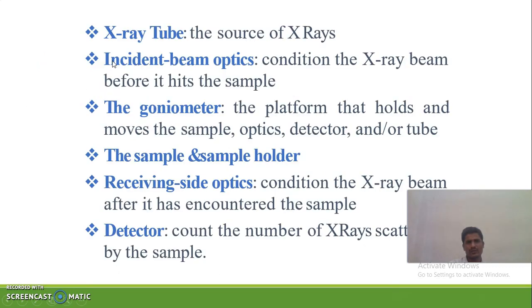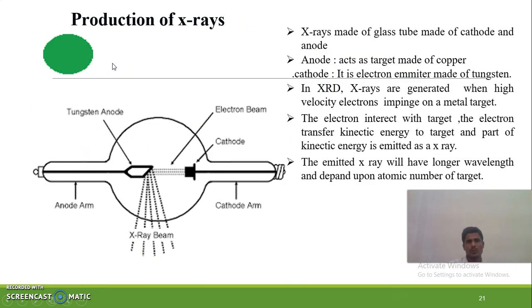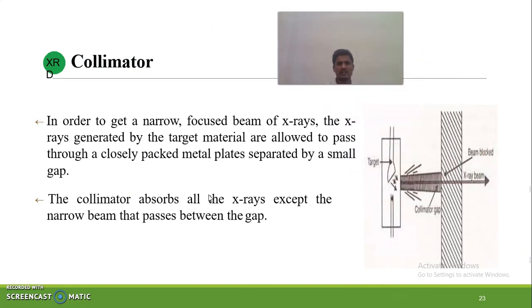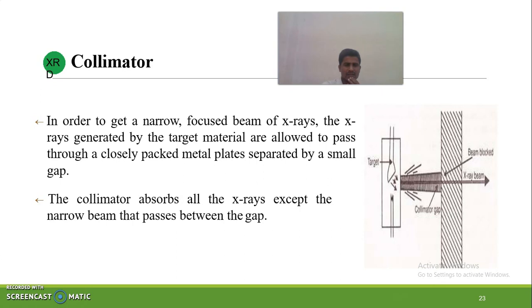The role of the collimator: whatever the X-ray beam produced is not narrow — it is broad. In order to obtain a narrow beam, it must pass through a small collimator. The collimator absorbs all the X-rays except for the narrow beam that passes through the gaps. Broad X-rays are absorbed, and the narrow beam passes through.